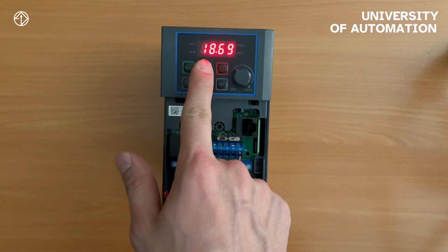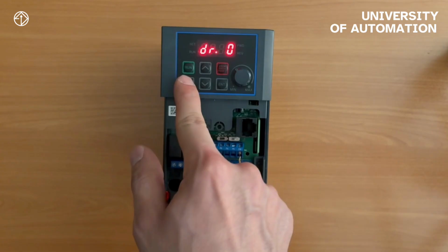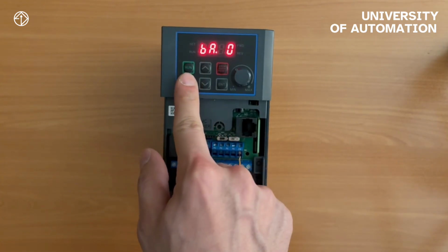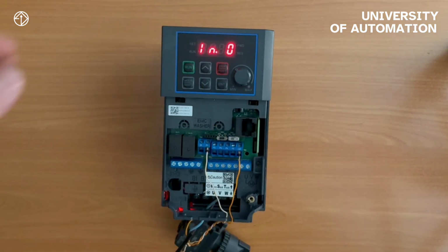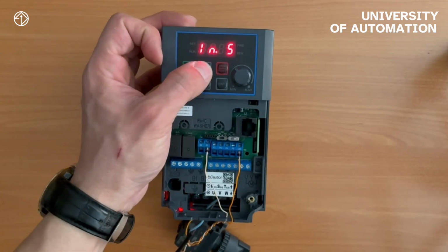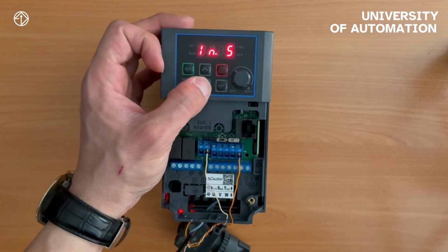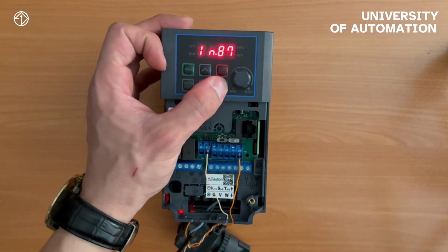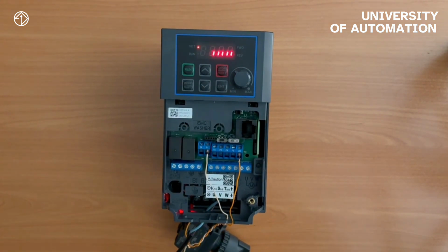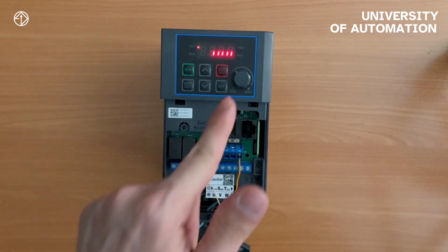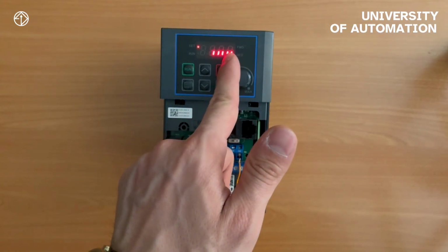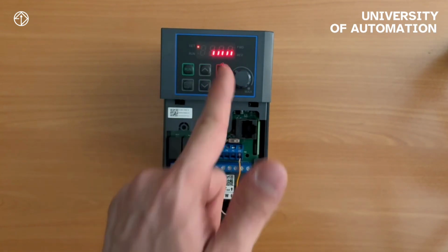All right, as we said, in parameter 87, I'm going to parameter 87. We said that with parameter 87, we can determine for the corresponding digital input whether it should be in normally open or normally closed mode. We said the first bit from the right becomes P1, then P2, P3, P4, and P5 in order.